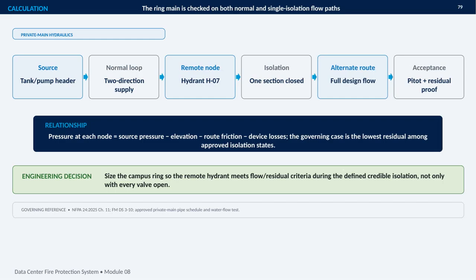This calculation checks the private main ring under 2 operating conditions: normal flow, with supply available in both directions, and a credible single isolation condition, where one section is closed. The governing case is the lowest residual pressure at any remote node across the approved isolation states. The hydraulic relationship is straightforward, but every term matters. Pressure at a node starts with source pressure from the tank and pump header, then decreases because of elevation, friction along the selected route, and losses through devices. The alternate route must still deliver the full design flow when a section is isolated, rather than relying on the convenience of having every valve open.